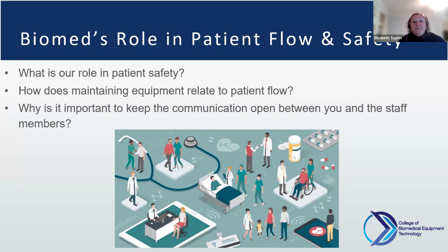So really what our role in patient safety is, the things that both Bianca and Elias had just mentioned, but also we're responsible for as soon as that medical device comes through the door, we need to make sure that it's safe for patient care. So medical device manufacturers and system manufacturers as well really need to produce quality equipment. But between when it leaves their dock and when it comes to the hospital's door or the healthcare organization's front door, biomeds are the first ones that are going to touch it. So we're opening the box, making sure that it didn't get damaged during shipment. We're making sure that it's configured appropriately for patient use, making sure that, for example, if it's something that has alarms, that the alarms are configured in a way that it's safe for patients.